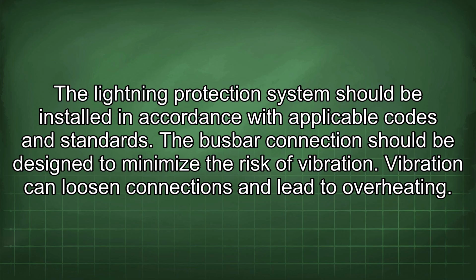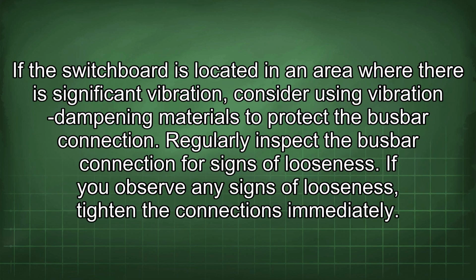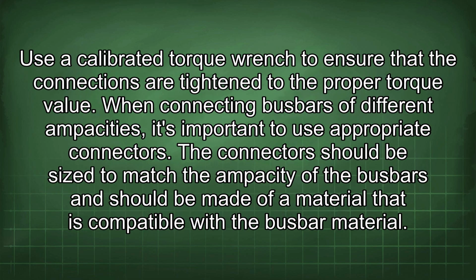The busbar connection should be designed to minimize the risk of vibration. Vibration can loosen connections and lead to overheating. If the switchboard is located in an area where there is significant vibration, consider using vibration dampening materials to protect the busbar connection. Regularly inspect the busbar connection for signs of looseness. If you observe any signs of looseness, tighten the connections immediately. Use a calibrated torque wrench to ensure that the connections are tightened to the proper torque value.